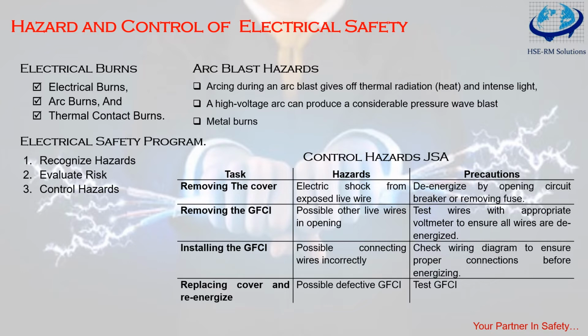A high voltage arc can produce a considerable pressure wave blast. A person 2 feet away from a 25,000 ampere arc feels a force of 480 pounds, approximately 200 kg plus, on the front of the body. So imagine you have been pushed by a 200 kg sumo kind of man. What will happen? In addition, such an explosion can cause ear damage and memory loss due to concussion. Sometimes the pressure wave throws the victim away from the arc blast. While this may reduce further exposure to the thermal energy, serious physical injury may result.